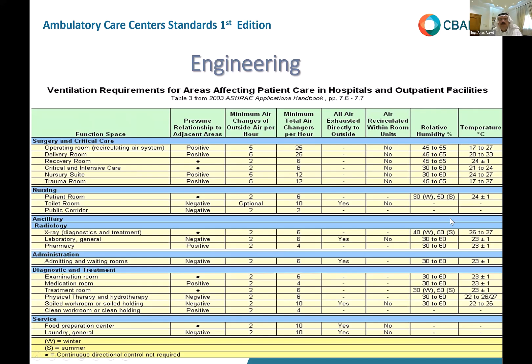And you can see in the operating theaters here, the number goes to 20 and 25 air changes. Okay. However, in the examination rooms, only 6. Because of the high level of the OR, we're giving it higher. That's not us, that's the ASHRAE. Also, it specifies the humidity within the examination room. Still, this is to be applicable, and you need to have 40 to 60 or 40 to 50 humidity within the room itself. You are in Riyadh, for example, this is very difficult to achieve. If you are in Jeddah or Dammam, it's very easy, but still you need to make sure the humidity is there.